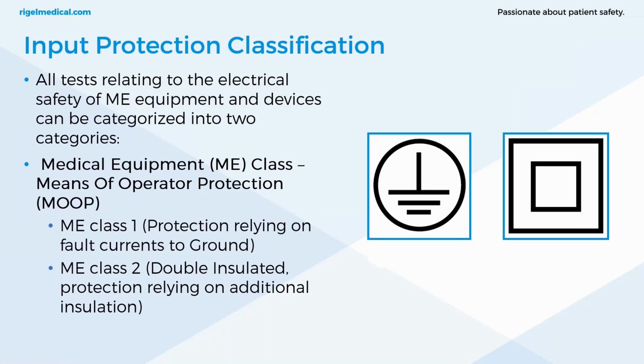So all tests are for electrical medical equipment that can be divided into 2 categories. We've got class 1, which is earthed, and class 2, which is double insulated, which we spoke about in the first couple of slides. The symbol on the left is for class 1, and the one on the right is class 2. These are typically found on the rear of the instrument, close to the power supply. Sometimes class 1 will be symbolized with an equipotential symbol, which is just like this, but with an upside down triangle at the bottom. If you're unsure of what class the device is, then you'll need to contact the manufacturer or look at the service manual, but typically this will be highlighted.